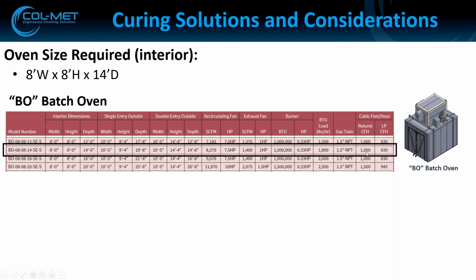It also shows you the gas requirements, as far as cubic feet per hour needed, which is really important to make sure the customer has the required pressure and volume of gas available. Another thing to look at is the gas train - this has a 1.5 inch pipe inlet, which means you'd want a minimum of a 1.5 feed line of gas coming in, or larger depending on the distance.